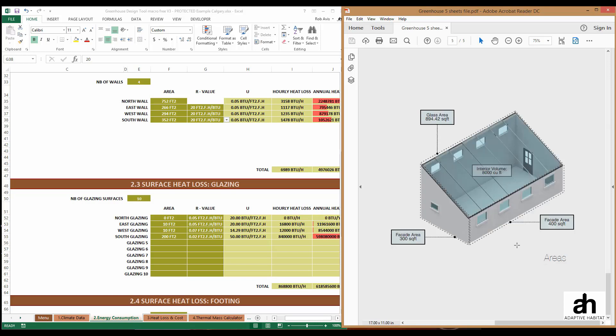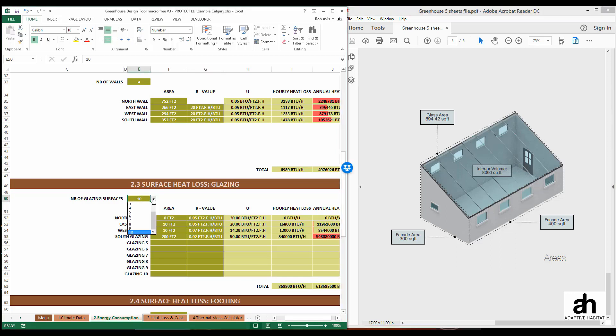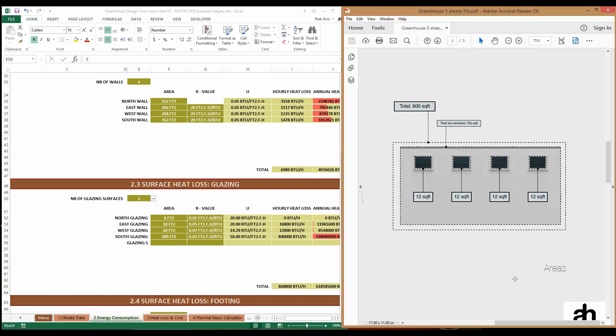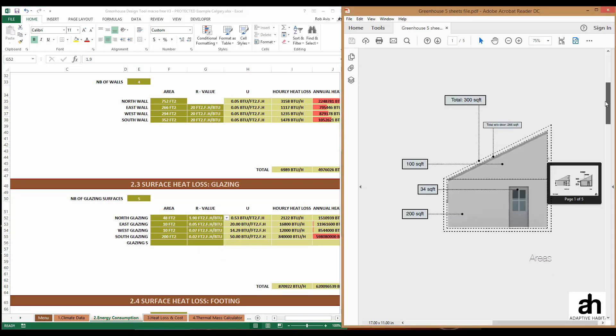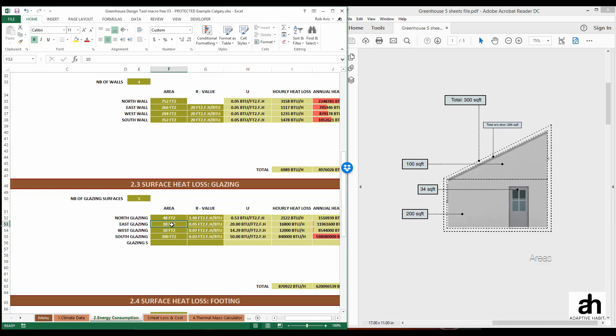When we look at the model, we can see we've got a south, west, north, and east glazing surface. Starting with the north, the total area for windows is 4 times 12, which is 48 square feet, and we're going to choose an R value of 1.9, which is the R value of the polycarbonate we've chosen. For the east glazing, we're going to put in the R value for the door and its area of 34 square feet, and we're going to choose a net R value of 8. For the west glazing, we have 6 square feet, and we're going to choose an R value of 1.9.